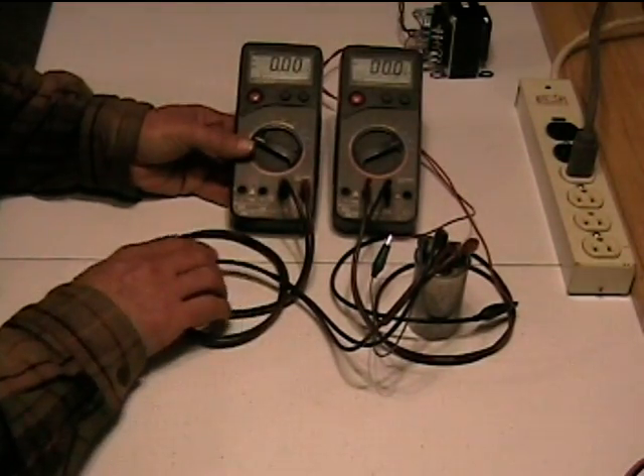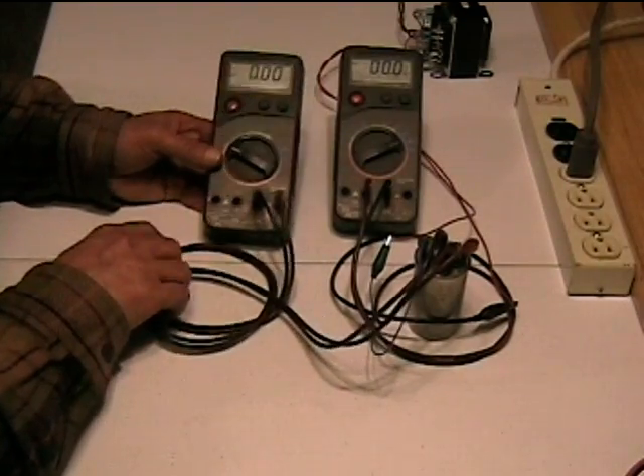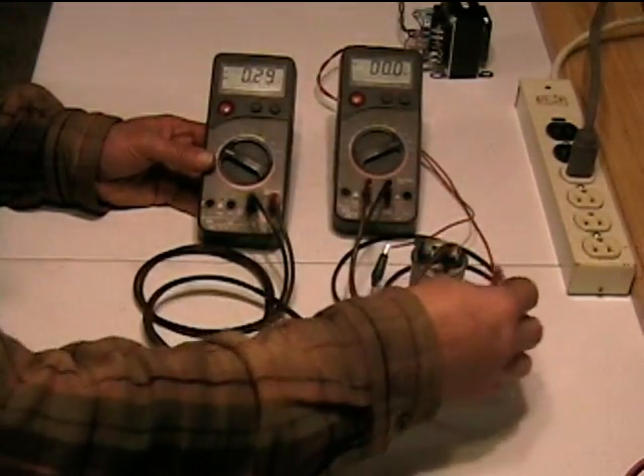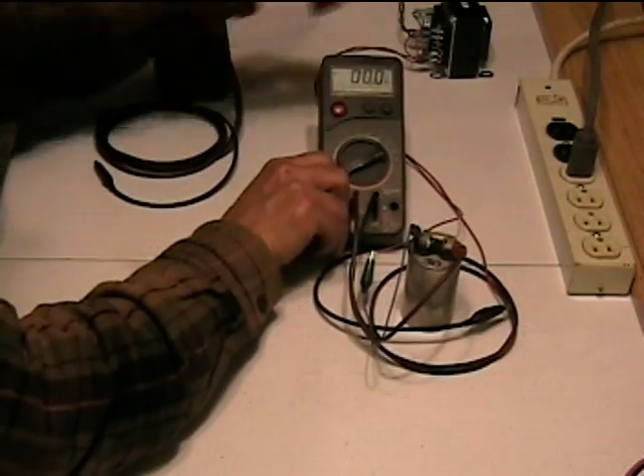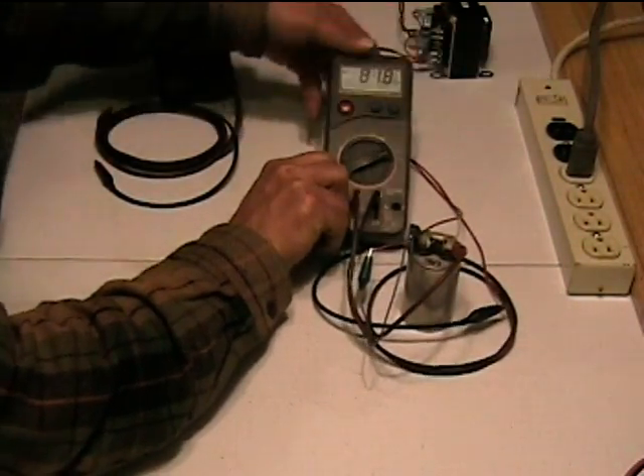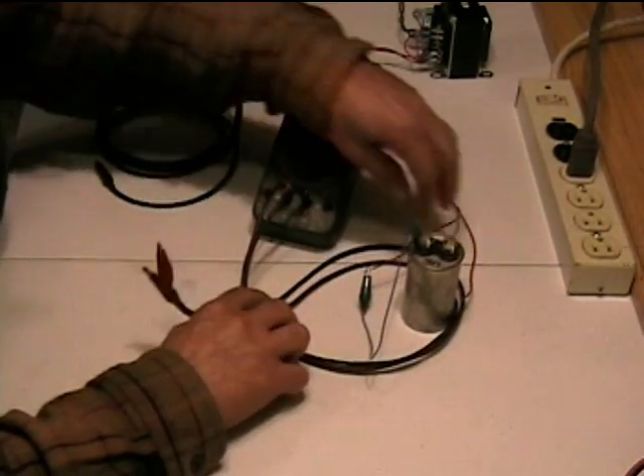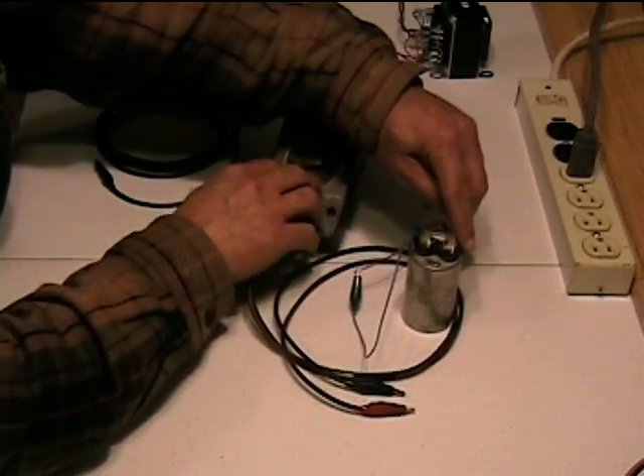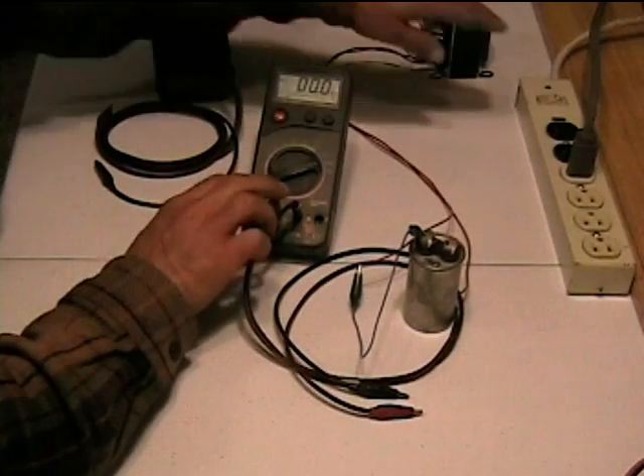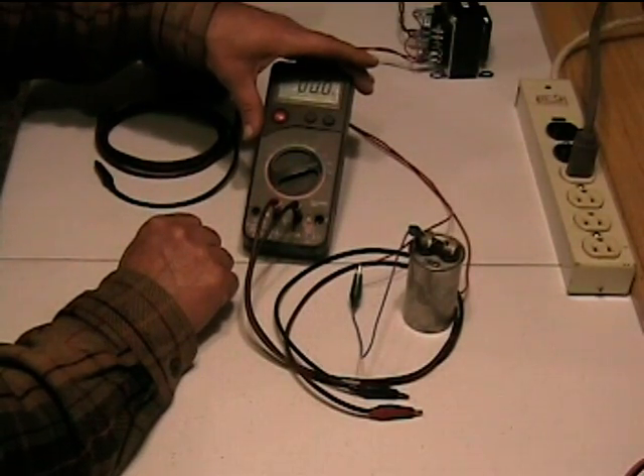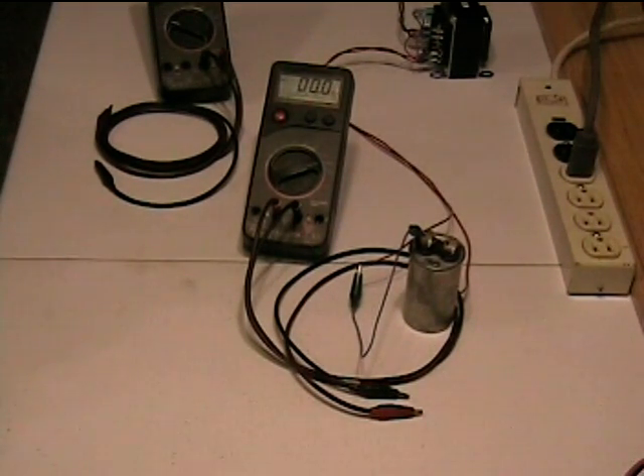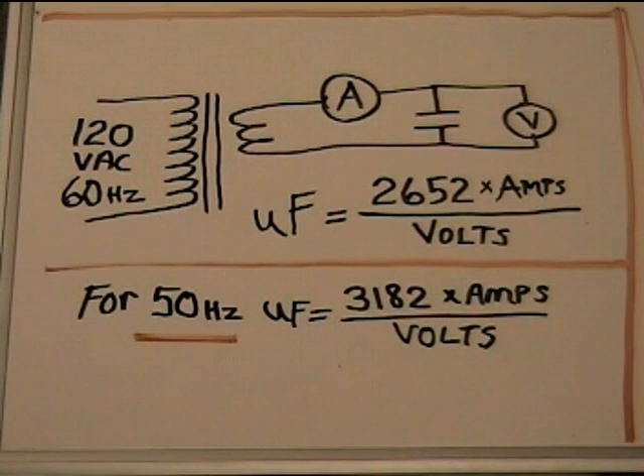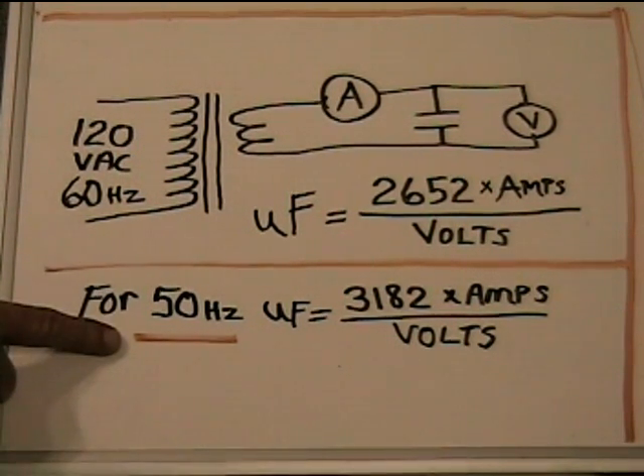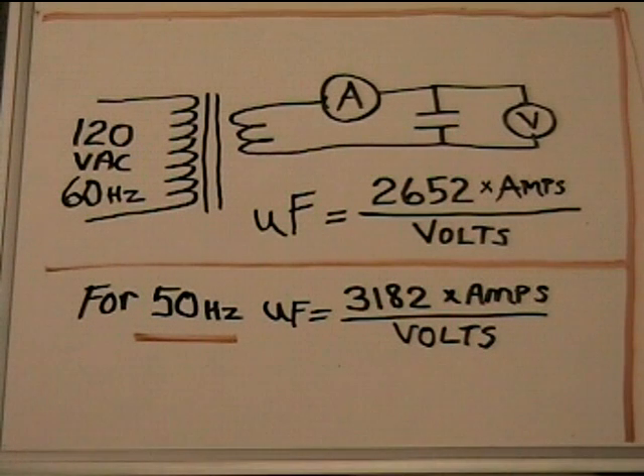Now, if you don't happen to have two meters, and I happen to have two here, and they wouldn't have to be matching by any means, you can certainly do the test with just one. You would connect up your one meter as an ammeter, as I showed you initially. Turn it on, get your amperage reading, turn it back off, disconnect the meter from the circuit, and connect your power source directly across the capacitor, reconfigure your meter for voltage, and connect it as a voltmeter across the capacitor. Turn the power supply back on again briefly to get a voltage reading, and then plug those values into the formula, and you're good to go. And for those of you in a location where the power supply is 50 Hertz, modify your formula and use the constant 3182. That accounts for the different impedance of the capacitor at the lower power line frequency.